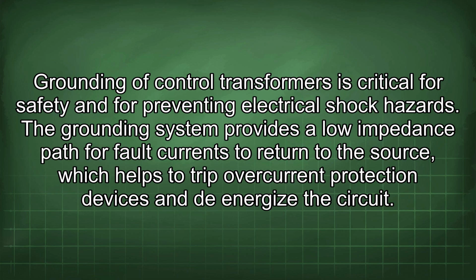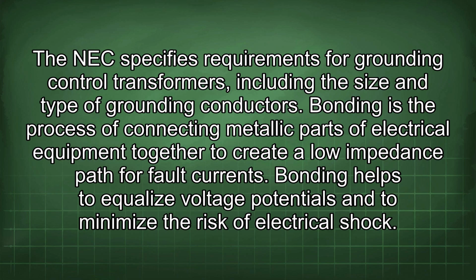Grounding of control transformers is critical for safety and for preventing electrical shock hazards. The grounding system provides a low impedance path for fault currents to return to the source, which helps to trip overcurrent protection devices and de-energize the circuit. The NEC specifies requirements for grounding control transformers, including the size and type of grounding conductors.